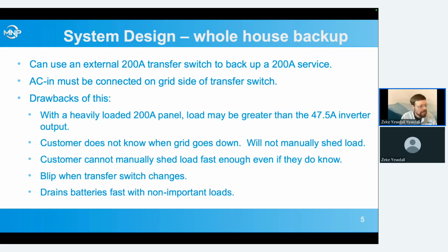With really heavy loads, if they're running at the time that the grid goes down, the customer can't even manually shed them fast enough, even if they know the grid goes down. So if you're pulling, say, 85 amps from the grid and it goes down and that transfer switch clicks over, unless that customer's standing there right with his hand ready to flip off that breaker to the heavy load, can't get it fast enough to prevent overload.